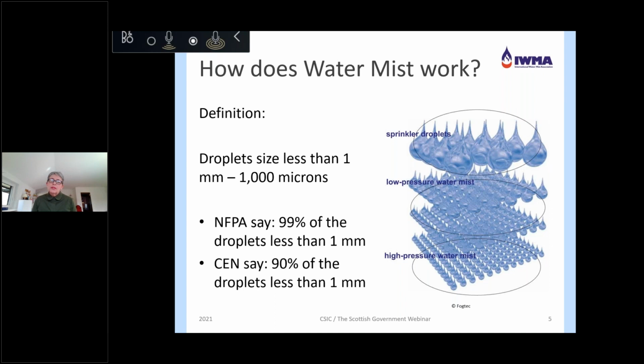So how does that all fit together? What happens if a fire breaks out and the water mist system is activated? Water mist attacks the fire by spraying water through nozzles especially designed for this purpose, and the smaller the droplets, the larger the overall surface. I think you can see that very well on the right-hand side. After a system has been activated, the released droplets evaporate and turn into steam. It is this steam or fog or mist, or whatever you want to call it, that interacts with the fire. Due to the enormous increase in the volume of the water droplets as they evaporate, the oxygen is displaced at the source of the fire and the flames are extinguished.